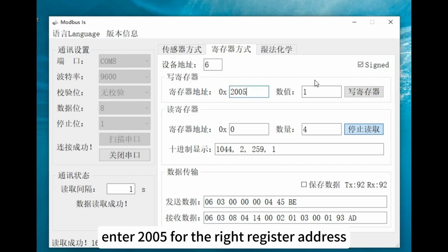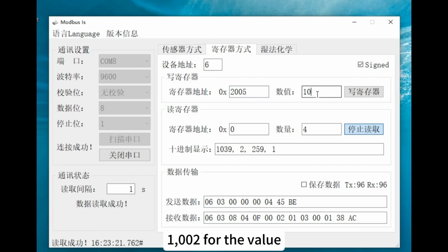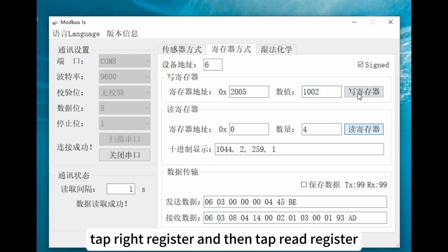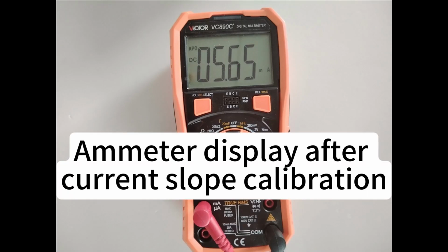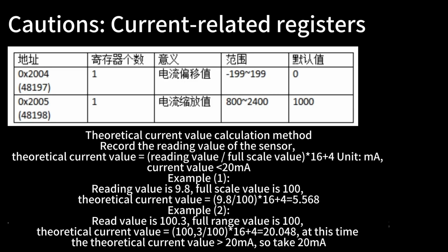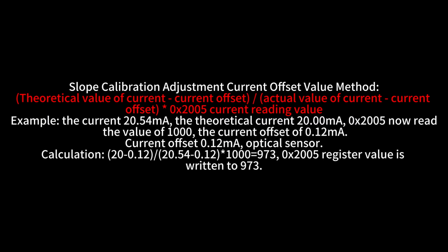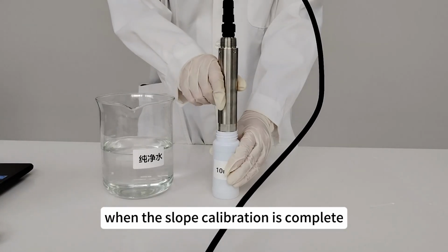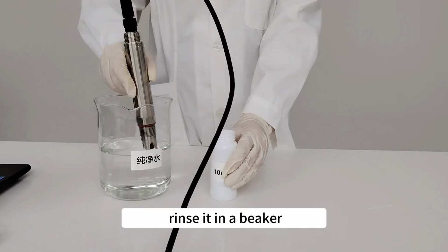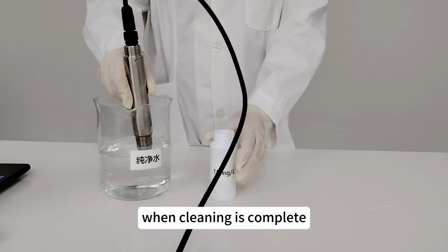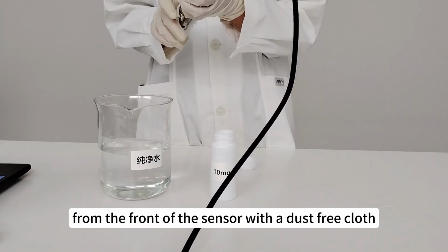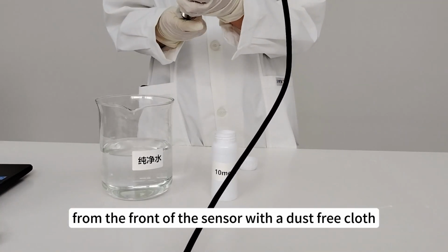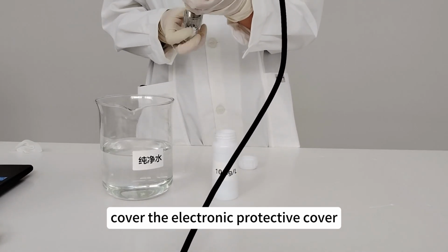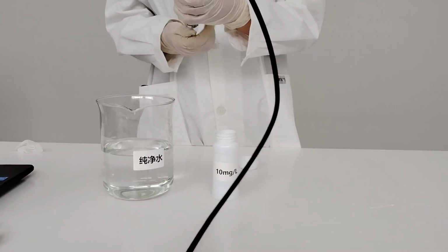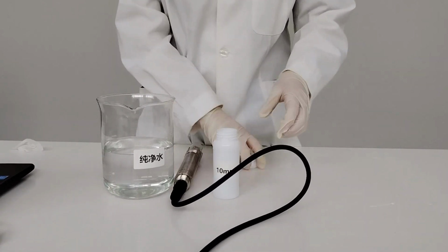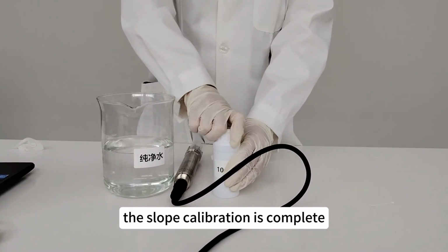Enter 2005 for the write register address, 1002 for the value. Tap write register, and then tap read register. When the slope calibration is complete, remove the sensor from the standard solution and rinse it in a beaker with purified water. When cleaning is complete, wipe the water from the front of the sensor with a dust-free cloth. Cover the electrode protective cover. The slope calibration is complete.